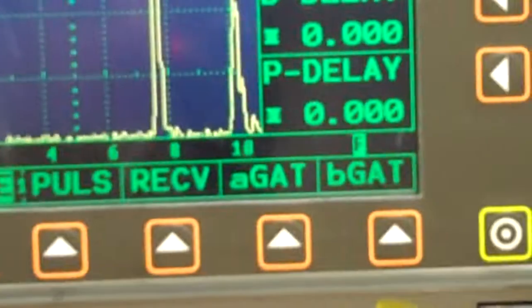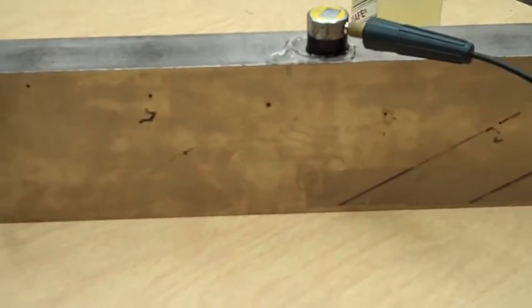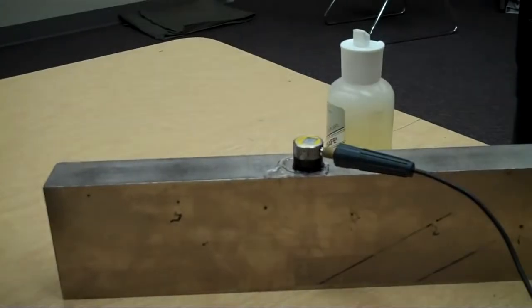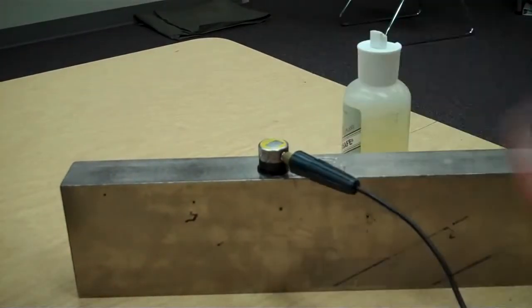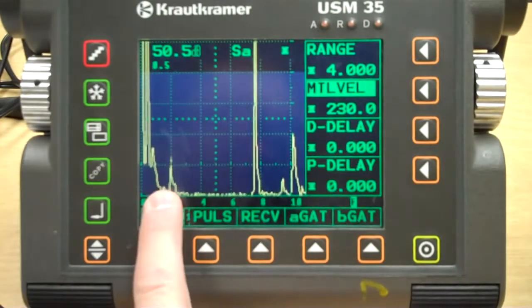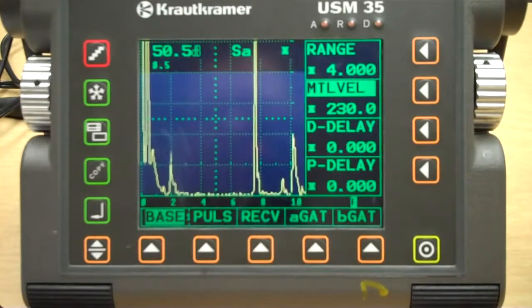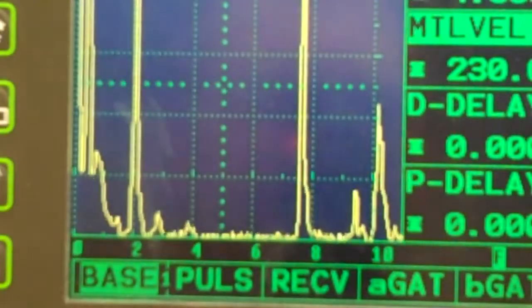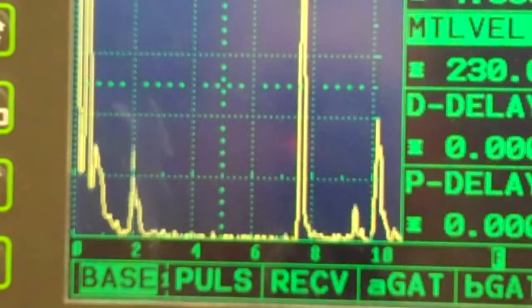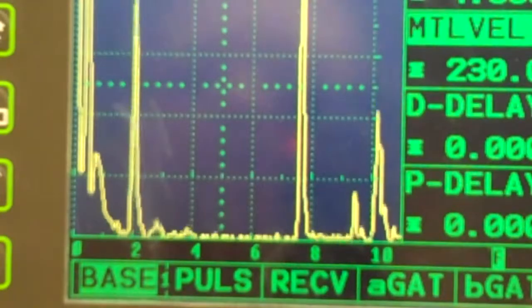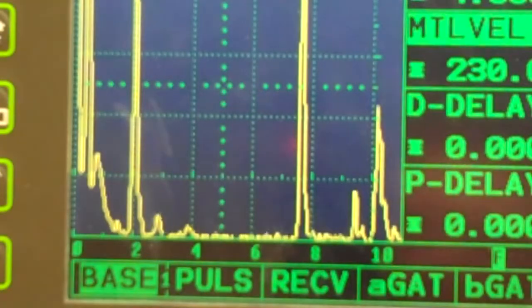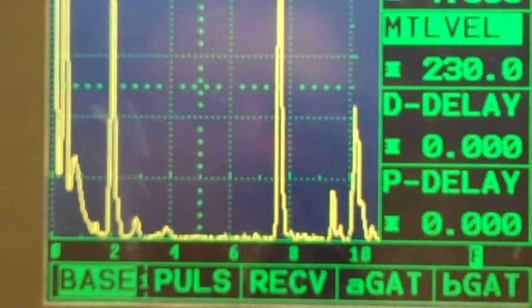Then if I come over here, I just want to measure 2 of the holes on the block. So it doesn't matter which 2. I'm going to back out a little bit here. You can see all the holes in the block. Okay, we're going to go to this one. Moving back over here. So there is our signal right here, coming right up about 19% full screen width. I'm just moving the transducer back and forth a little bit. I'm going to zoom in for you so you can see that 19%. I'm just moving back and forth over the hole on the block. So peak it up there, coming up about 19%. So that's the first one you need to measure, 19% of 4 inches.